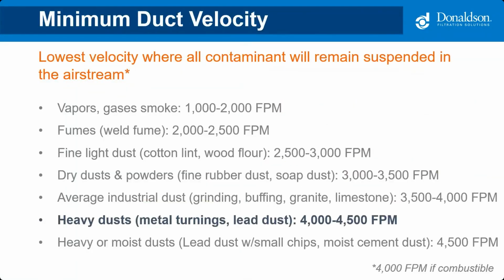The minimum duct velocity is a critical design factor. It's the lowest velocity where all contaminant will remain suspended in the airstream. If you go below this velocity, dust could settle out within the ducts and cause other safety issues. Duct lines, no matter the size, must be full of air at the designed conveying velocity to avoid settling out. For many of the light dust generated in battery recycling, the industrial ventilation manual lists the minimum at 2,500 to 3,000 feet per minute. However, 4,000 feet per minute is the minimum duct velocity if the dust is combustible, which it typically is when we're talking about battery recycling. So you're going to see duct velocities in that 4,000 to 4,500 feet per minute range.